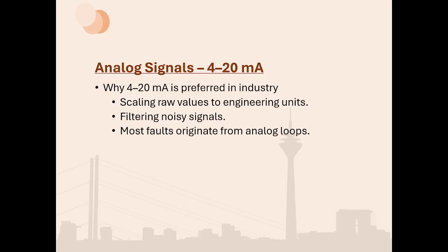They are not digital signals like zeros and ones. They vary continuously. You could have 1.1 psi and then it increases to 1.5. The most common analog signal used in the industry is the 4 to 20 milliamps. Engineers use this range because it is reliable and allows fault detection. If a signal drops below 4 milliamps, the system knows something is wrong. And this signal is sent from instruments like pressure transmitters to the PLC.